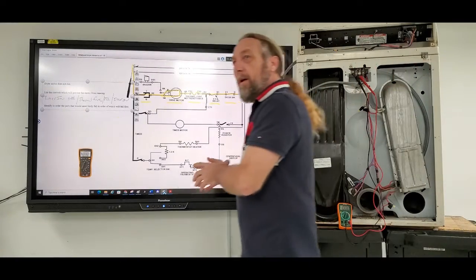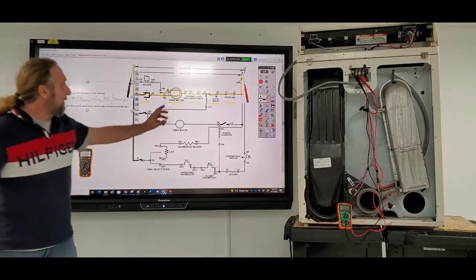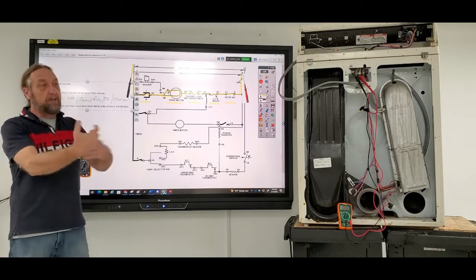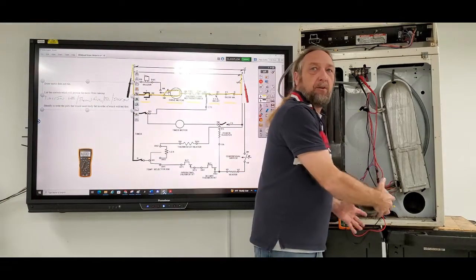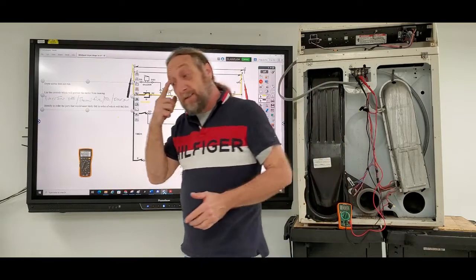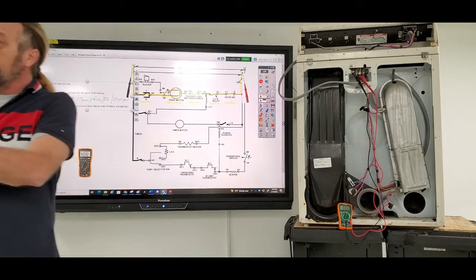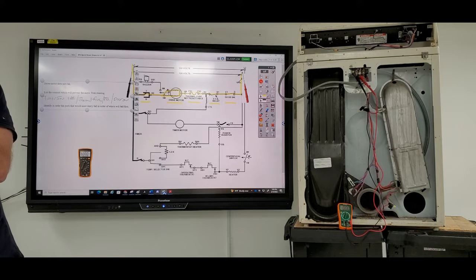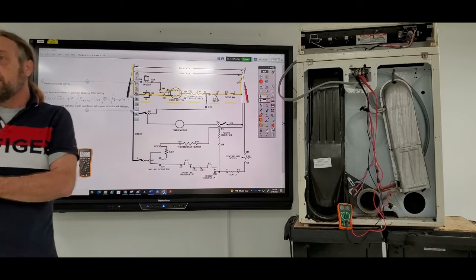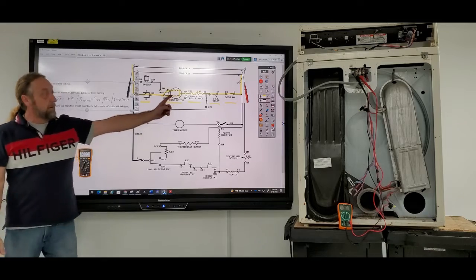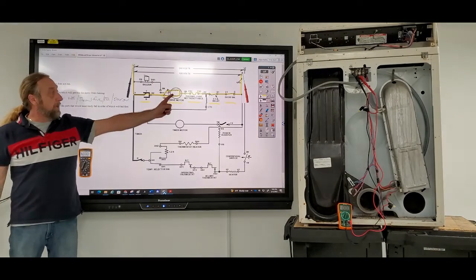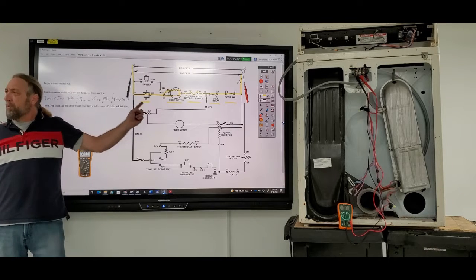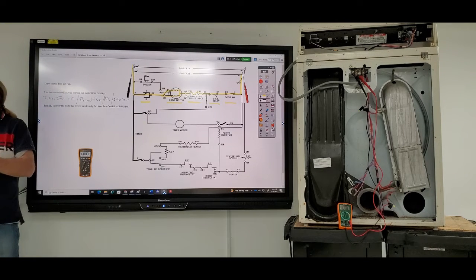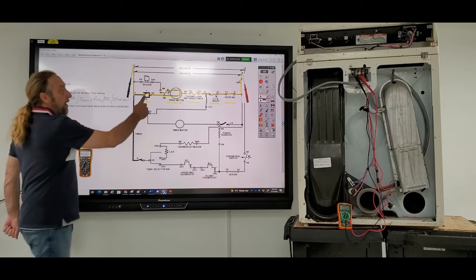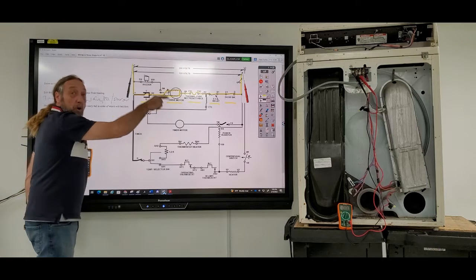So where's the closest point to the motor that I could test back here? If I needed you to go to the store, what's the next closest point between here and there that you'd be at? The timer switch — right, this timer switch here. What point on it would be next closest? RE. That's correct — RE is as close as you can get to the motor without going to the motor itself.